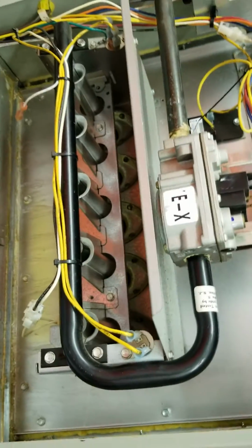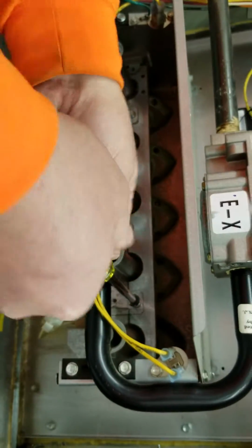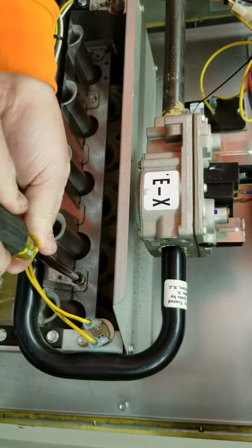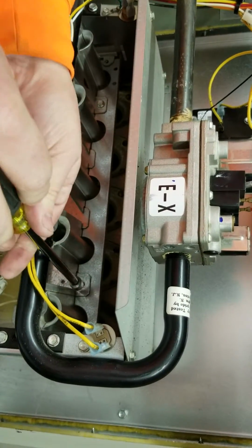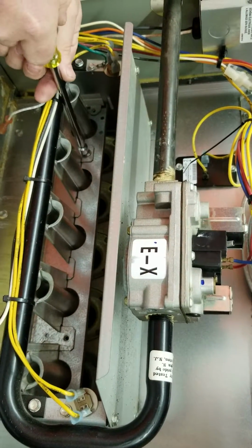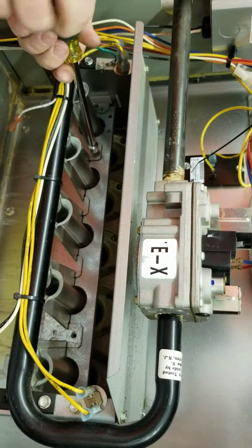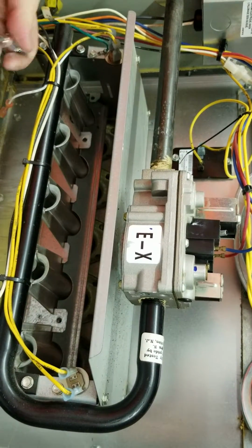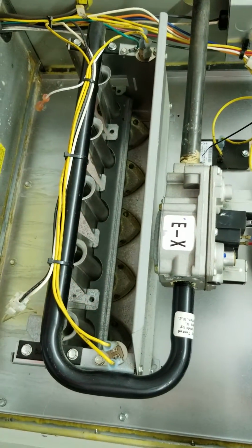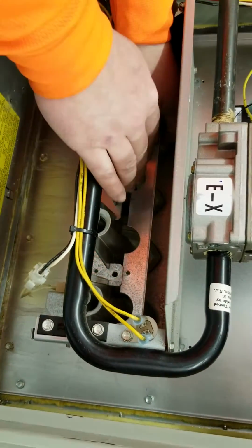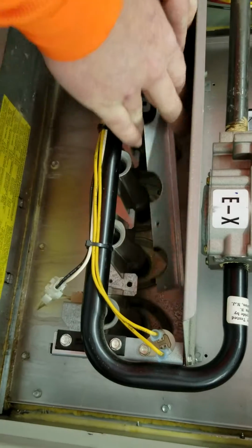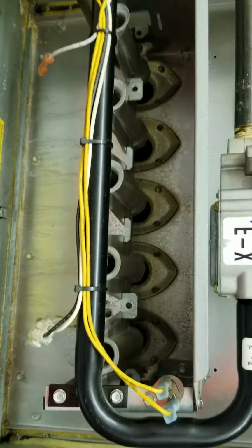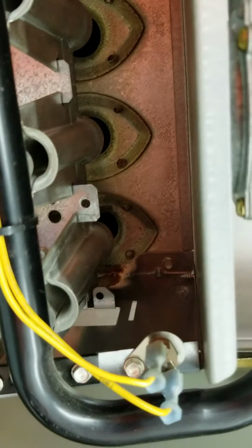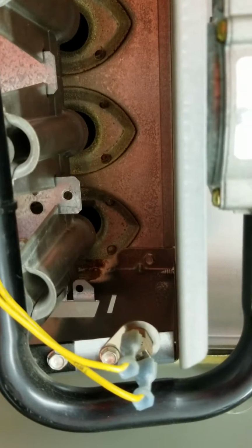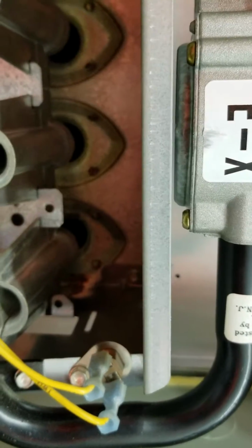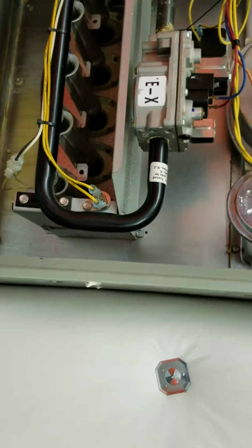Next step would be to remove the plate that holds the burners on. In this case it's 2 screws. Sometimes, depending on the size of the furnace, it might be 3 or more. Now, as you remove that plate, you'll want to be very careful because you have something in here called a hot surface igniter that is fragile. If you bump it the wrong way, it can break, and it is right there in front of, in this case, the far right burner. You might be able to see it, just barely. You'll be able to see it better once we pull the burners out.